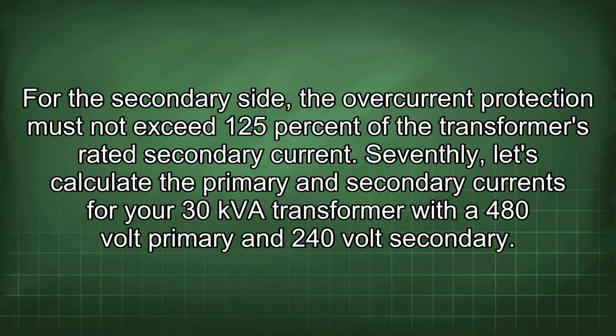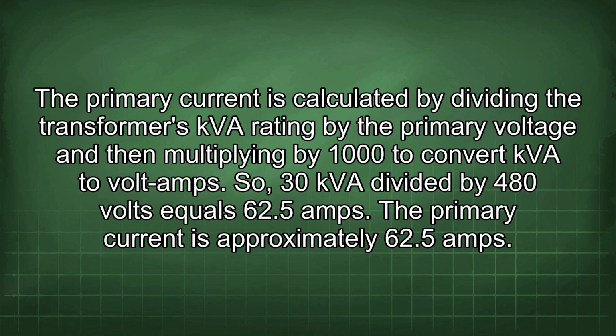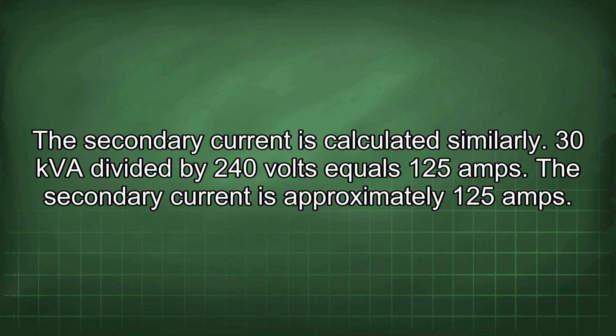Seventhly, let's calculate the primary and secondary currents for your 30 kVA transformer with a 480 volt primary and 240 volt secondary. The primary current is calculated by dividing the transformer's kVA rating by the primary voltage and then multiplying by 1000 to convert kVA to volt amps. So, 30 kVA divided by 480 volts equals 62.5 amps. The primary current is approximately 62.5 amps. The secondary current is calculated similarly. 30 kVA divided by 240 volts equals 125 amps. The secondary current is approximately 125 amps.